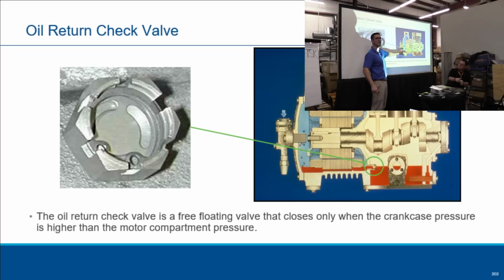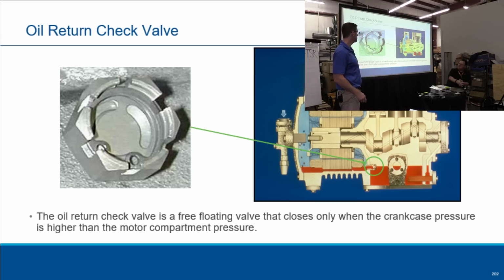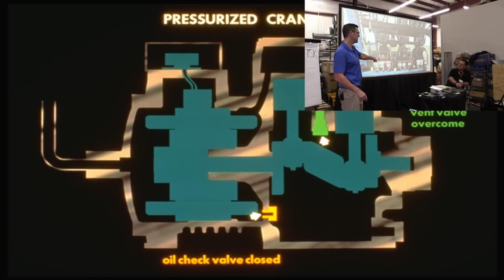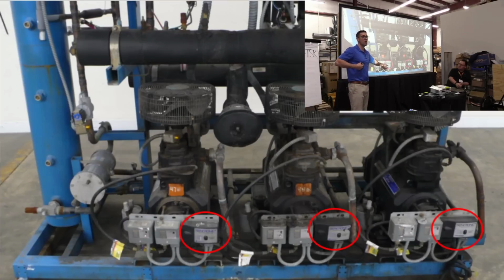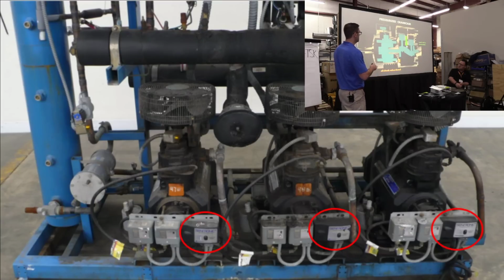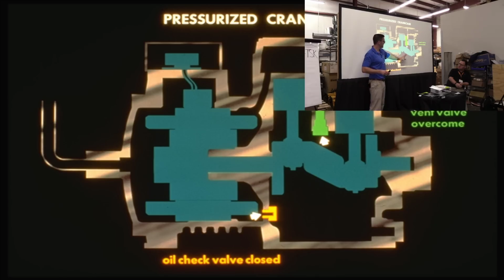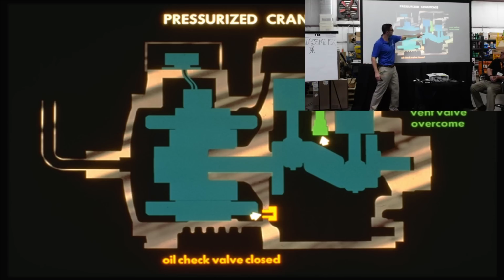Remember I talked about the check valve inside our 3D, 4D, 6D compressors? So we have a check valve, free floating. What's this down below here? Does anybody know what these are? Oil pressure control, Sentronic. They're all called CoreSense now. Okay? I mentioned to you guys earlier that your crank should be higher or lower pressure than your body. What should this be, lower or higher? Lower pressure. Higher pressure here, 2 psi. That's what this vent valve is for. So now I've got 2 psi higher. That oil, as it comes back, it flows, gets into my pump, and everything's good.